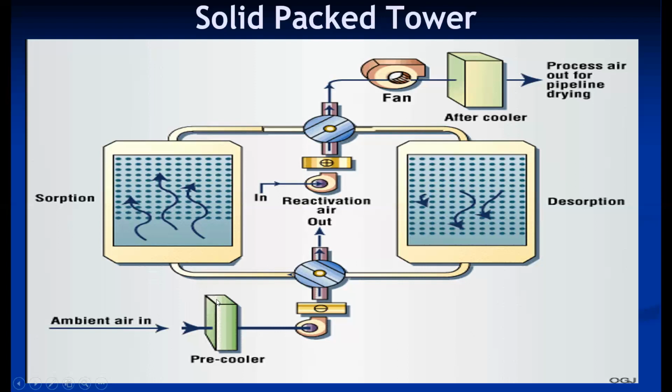A separate cooler is used for cooling purpose. So wherever the process is cooling and dehumidification, generally the cooler is required. If only dehumidification is required, then this system is sufficient. Otherwise, a separate cooler is required to remove the sensible heat from the ambient air.